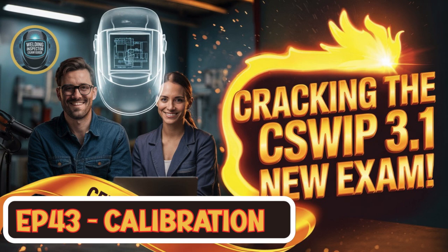Makes sense. So frequency, how often should this equipment get checked? Are we talking daily, weekly, yearly? BS EN 50504 gives recommendations. For standard grade gear, it's typically yearly, but that's only after an initial consistency check every 3 months for the first year. Okay, yearly after the first year. And for precision grade? For precision grade, which remember is for those more demanding jobs, it's recommended every 6 months, more frequent.